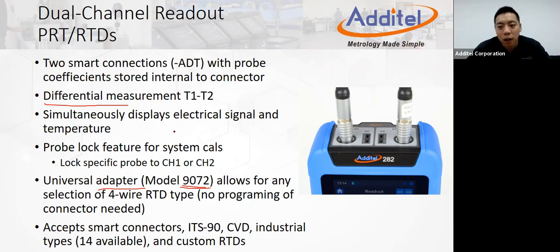On each channel of the display, we can have both the electrical measurement signal and the temperature signal. So we're going to have a value in degrees C, Kelvin, or Fahrenheit in the middle, and on the bottom of the channel, the ohm or millivolt value. We display those two values simultaneously.